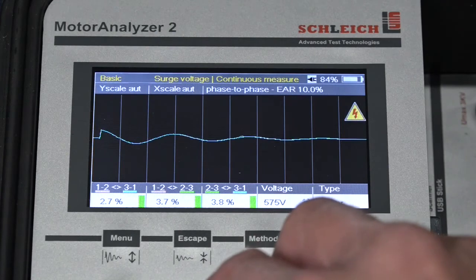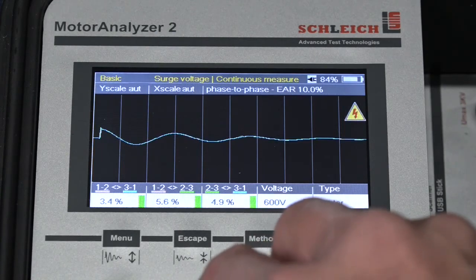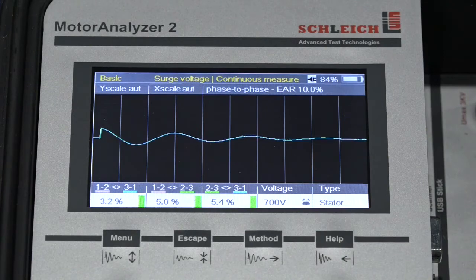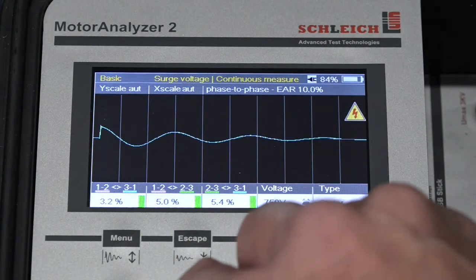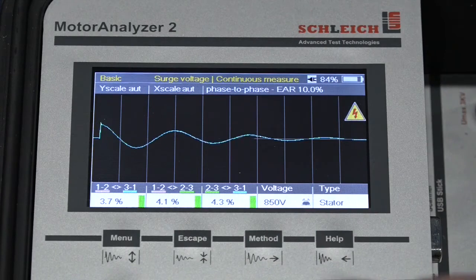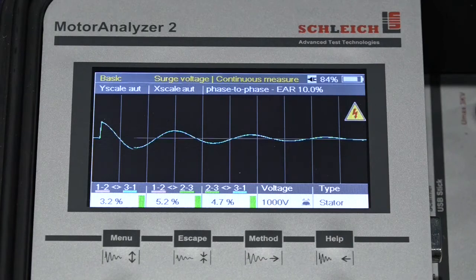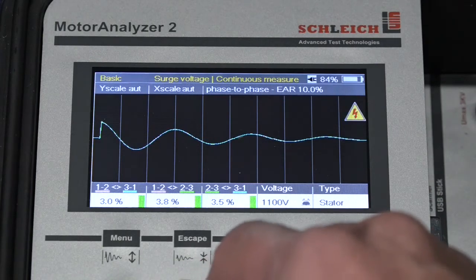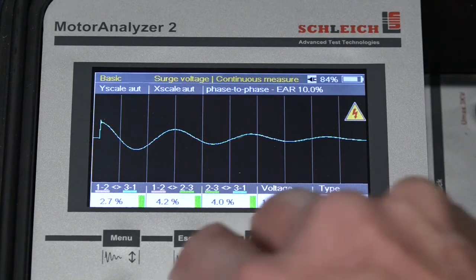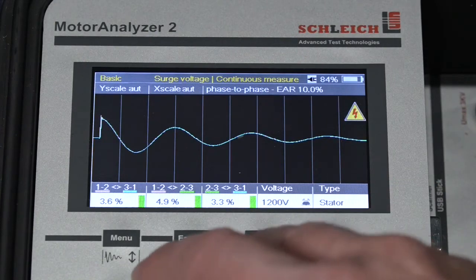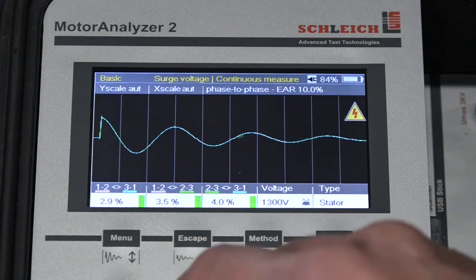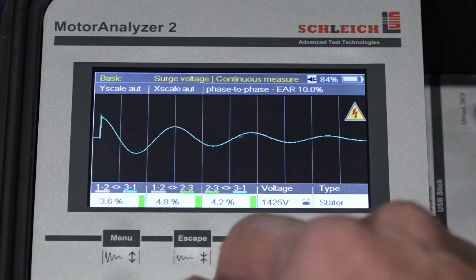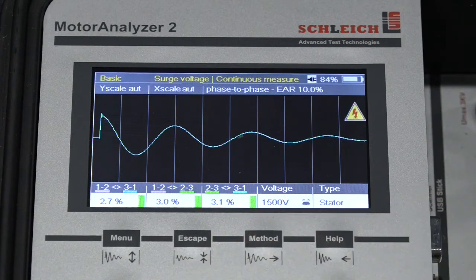Now it's in this mode. I can ramp up the voltage by hand. So this is very similar to what we've done in the past. So 1000 volts, I'll increase it to 1200. There we go. I'll increase it to 1300. There we go. Again, the waveforms are all sticking together, so there's no problem with this particular stator.